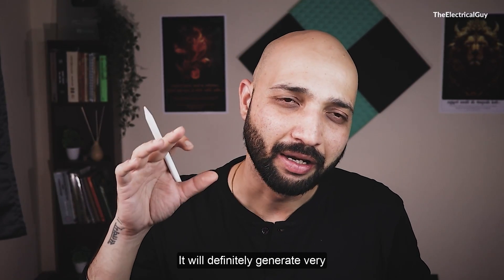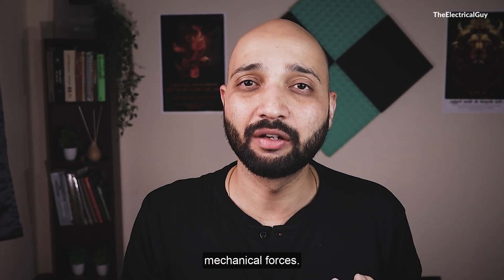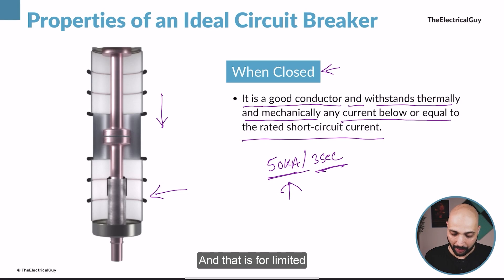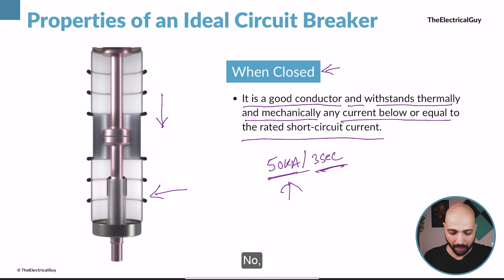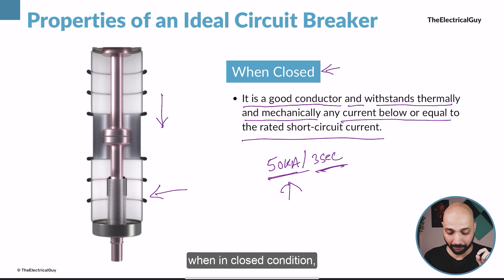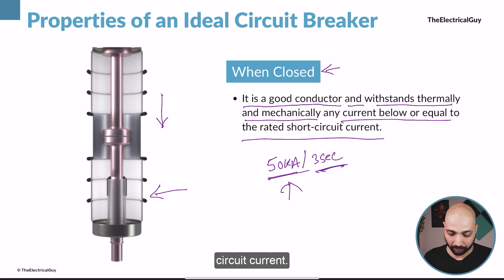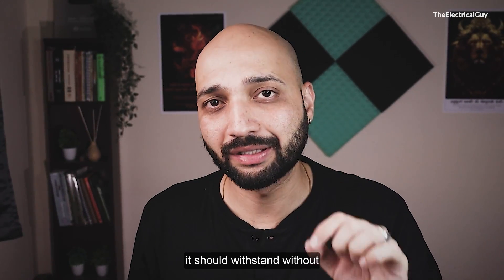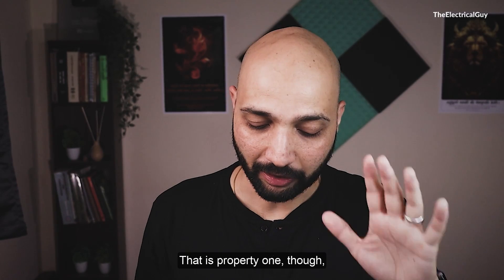At 50,000 amperes, very high thermal issues and mechanical forces are generated. The circuit breaker should withstand all of these without any issue. It is for a limited time period — 50 kilo amps won't flow for hours; a specific time is defined, such as 3 seconds or 1 second. So Property 1 is clear: a good conductor when in closed condition, withstanding thermally and mechanically any current at or below the rated short circuit current.